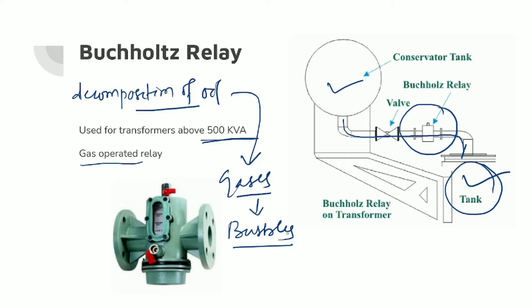These bubbles pass through the pipe connecting the transformer tank and the conservator tank. In this route, the Buchholz Relay is situated. Gas bubbles are trapped in the Buchholz Relay, thereby creating pressure inside it.